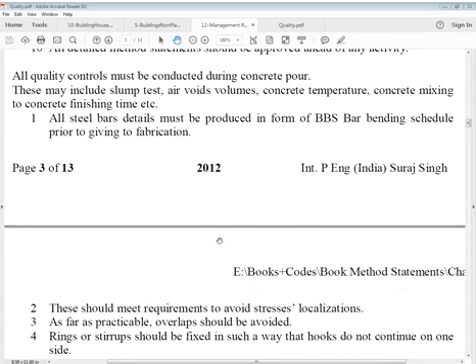The first requirement after delivery is that you have to store them properly, in such a way that they are neither affected by ground moisture nor by moisture available in the weather, environment and atmosphere, as well as no effect by rain. So these must be stored a little above ground, say 30 centimeter to 45 centimeter above ground, or to whatever extent possible. You can make a good platform by block work or by timber framing, and you can raise these parts from the ground and cover them with polythene sheet so that no moisture can affect them.